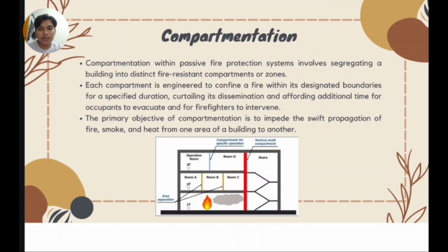Compartmentation. Compartmentation within a passive fire protection system involves segregating a building into distinct fire-resistant compartments or zones. Each compartment is engineered to confine a fire within its designated boundaries for a specific duration, curtailing its dissemination and affording additional time for occupants to evacuate and for firefighters to intervene.